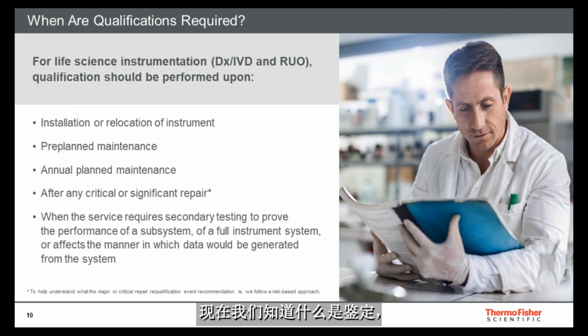Now that we know what a qualification is, we can ask, when are qualifications required? Installation or relocation should be points of common understanding. However, I find our other bullet points here can be less understood. Most of the life sciences instrumentation will have an annual planned maintenance recommendation. The focus of this is purely maintenance and to maintain performance within specifications. Examples of this are cleaning of optics, fans, thermal blocks, and associated computer maintenance such as defragmenting. After such an activity, it would be recommended to document the continued performance of the system as a requalification.